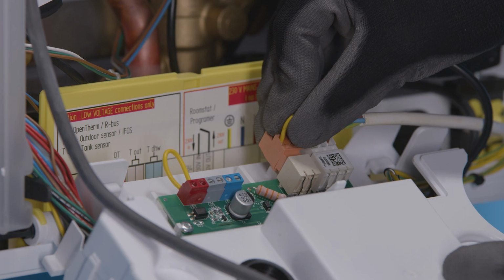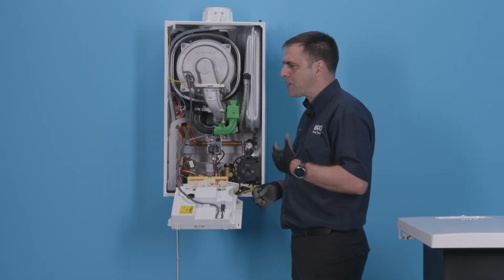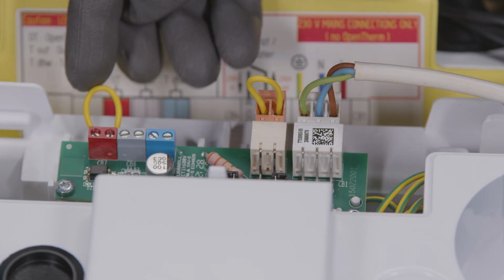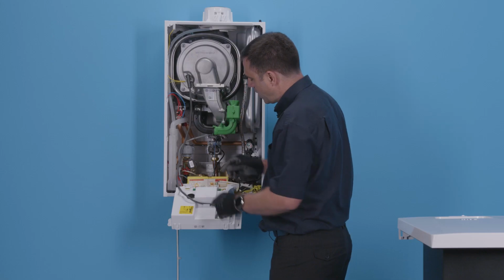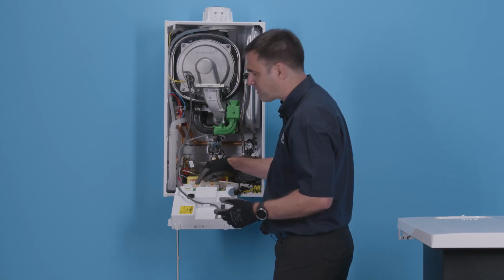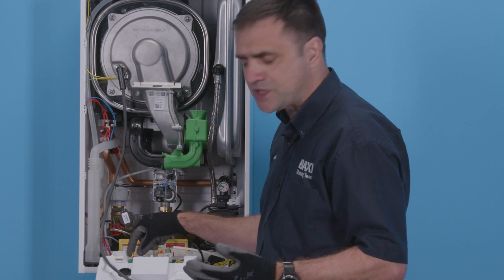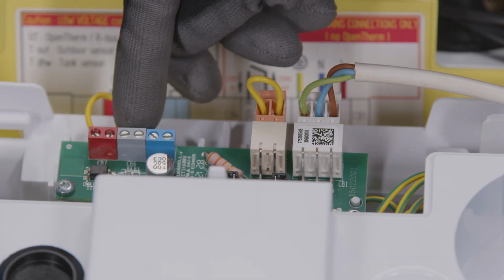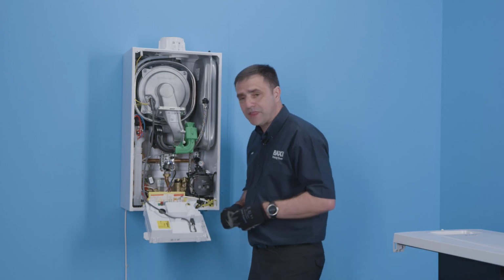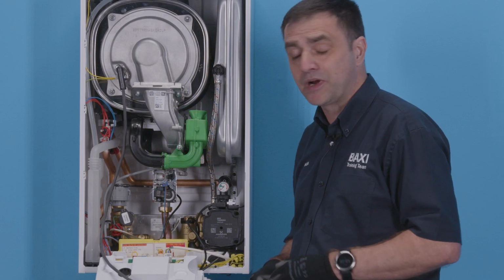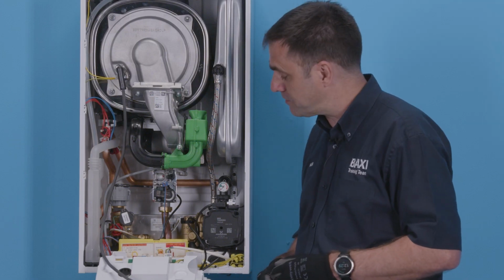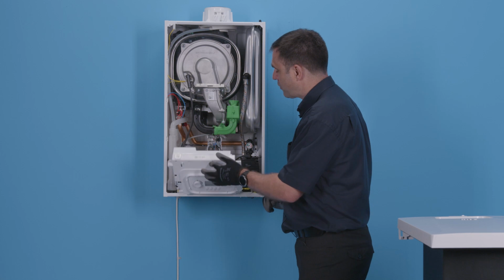If I am going to use low voltage, either for OpenTherm or maybe outdoor weather compensation, I'm using the low voltage side over here. And what I've got is my OpenTherm connection. If I'm going to use load compensation, that's on the red block, and here, the block next to it, the grey one, that's for my outdoor weather sensor. Polarity is irrelevant, just wiring them straight in. So now it's all wired up, let's move on to commissioning.